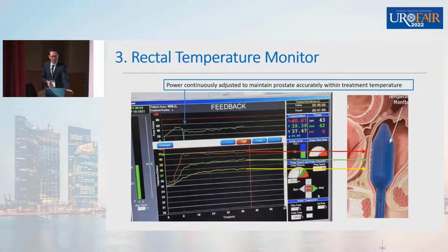Okay, so that's where the rectal probe is placed. 3 temperature probes give you 3 lines during the treatment process. And you can see, for example, at the beginning, the machine will heat up and the temperature will rise quite rapidly. We set the machine at 41, and the moment the temperature touches 41, it will signal to the machine to cut off. So you can see the machine actually suddenly switch off. So the prostate will cool down again.